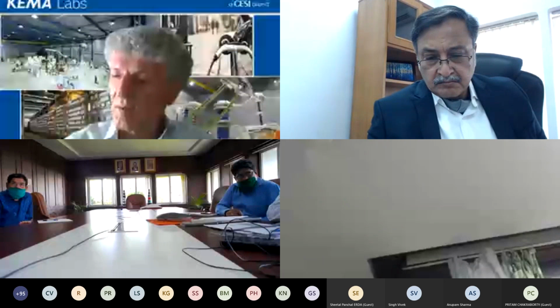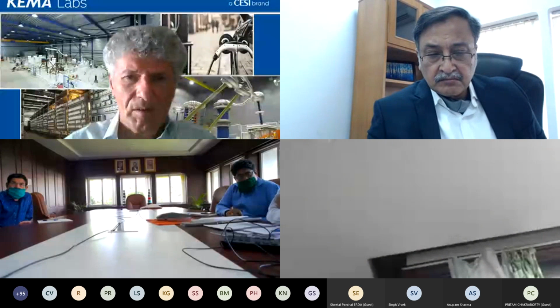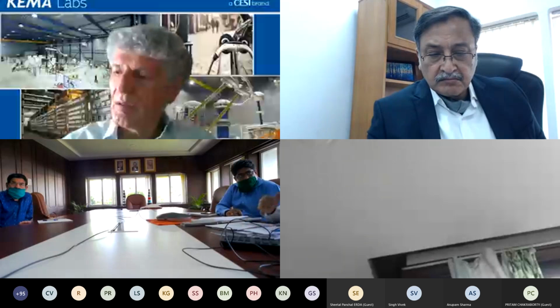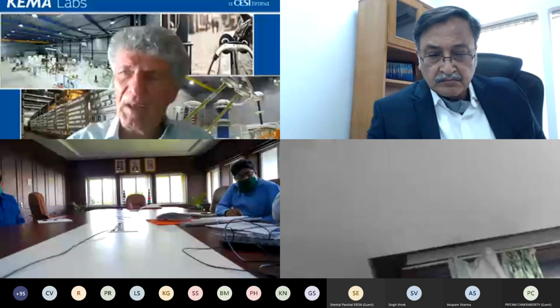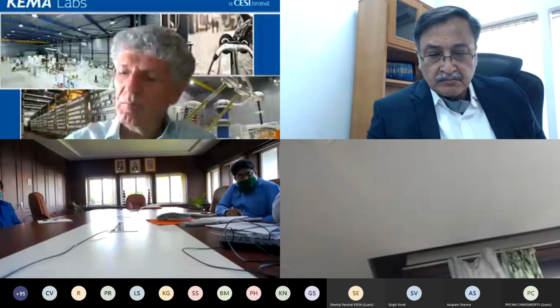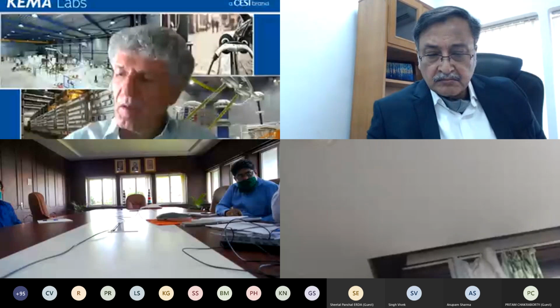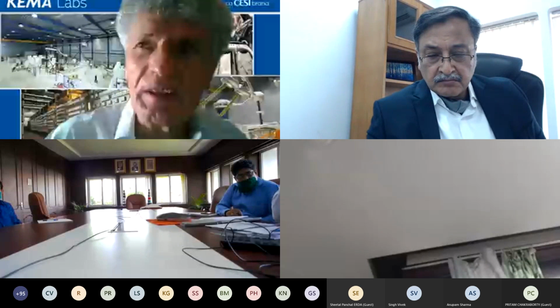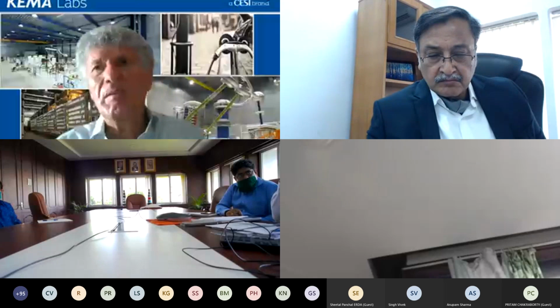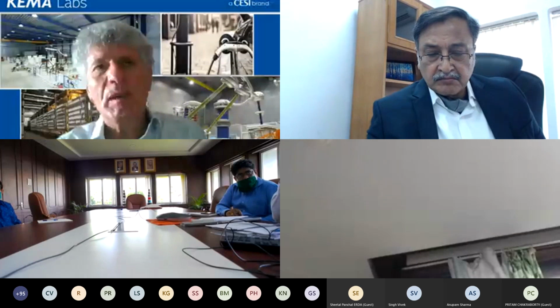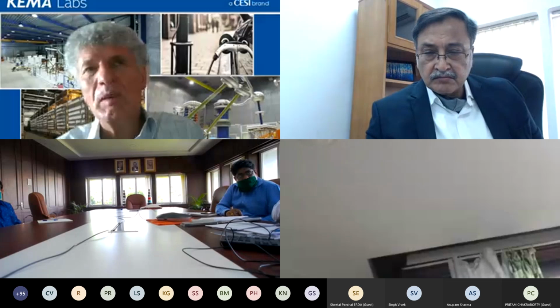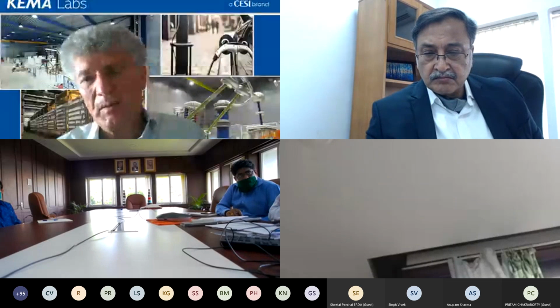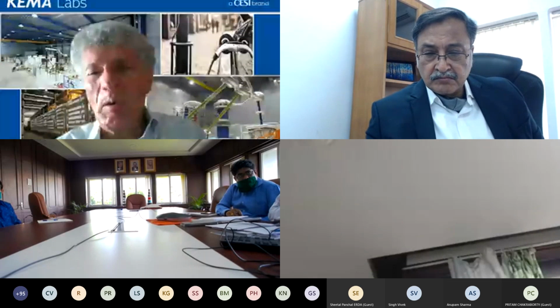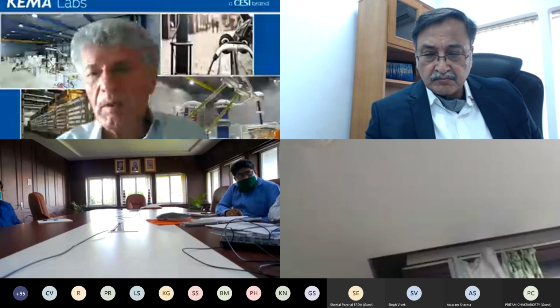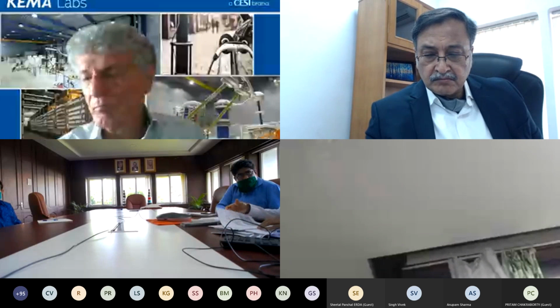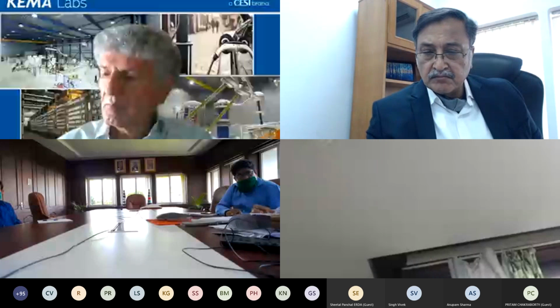This is Himanshu Joshi from ERDA. I want to ask about the tan delta measurement. Ambient temperature. You know, tan delta measurement is a very good measurement in case you want average information on the health of your connection, but it gives you no information at all on the localization of the point.